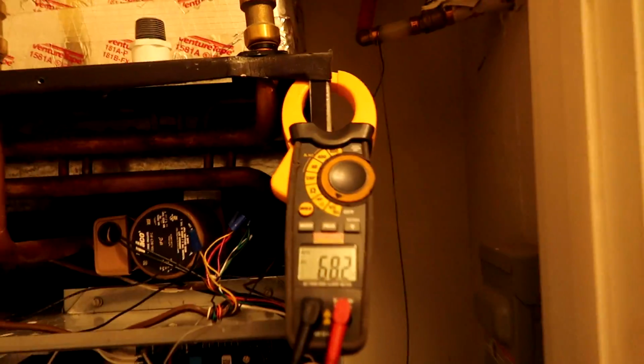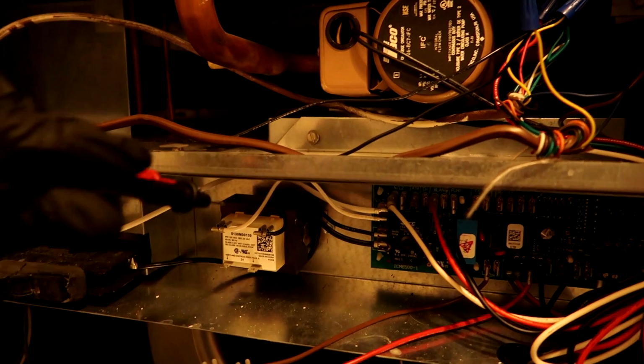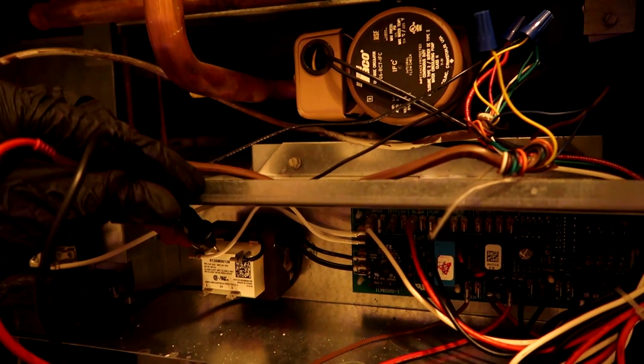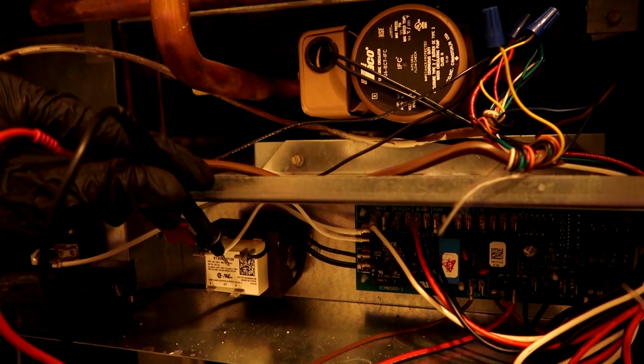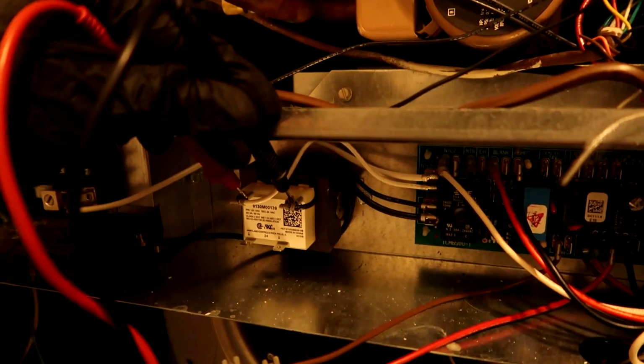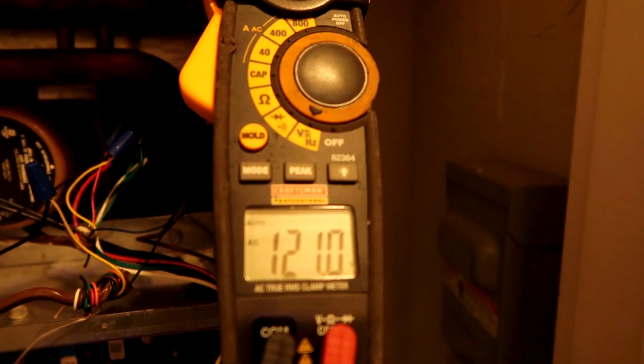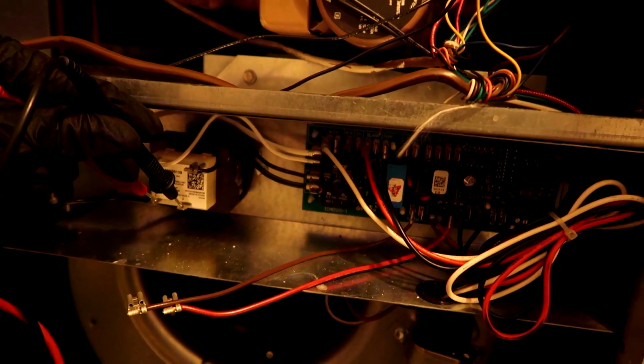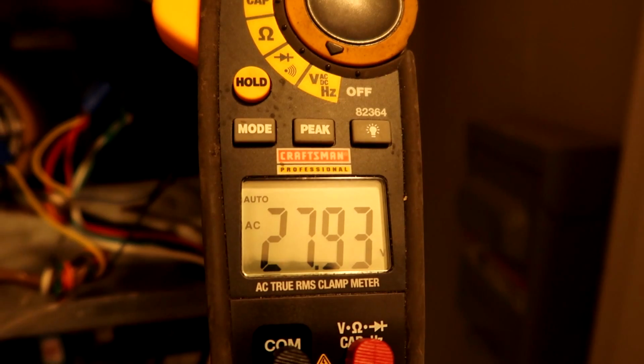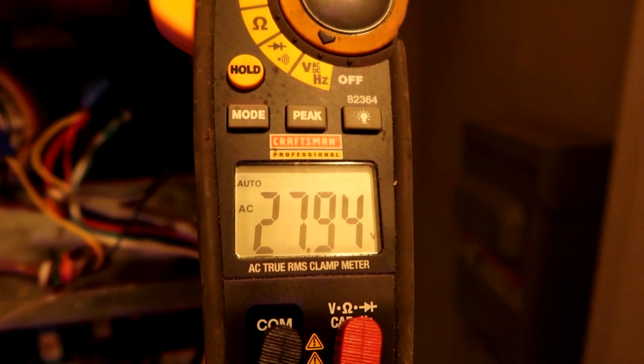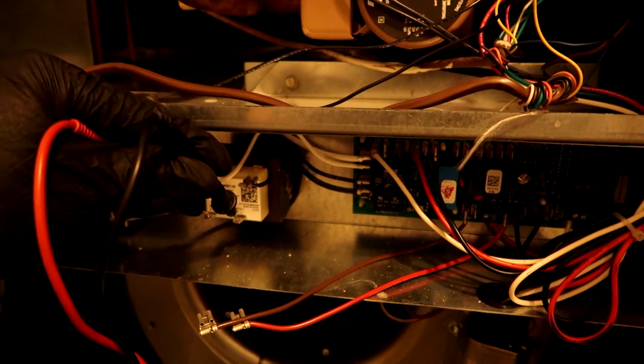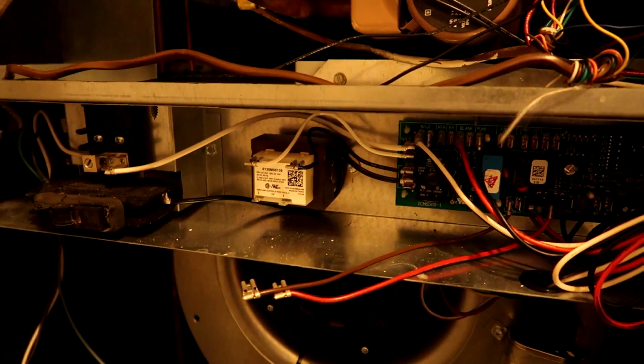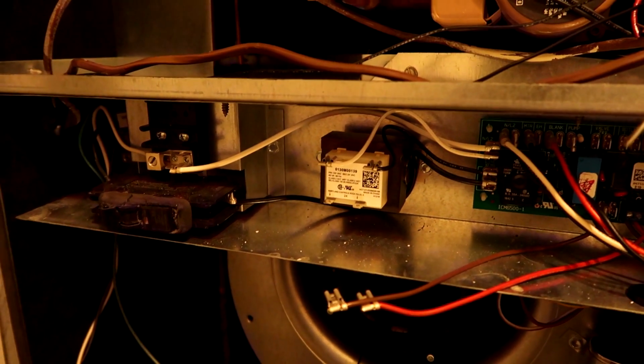Alright, Skid, we don't have any new transformers in the shop. Let's just see if we're getting high voltage here. Should have 120. Yep, 120, and we should have 24 volts coming out of the bottom, or around 24, 27. So the 27.9. So the transformer's still good. It was just heating up. That's what I smelled. I'm gonna roll the dice and hook it back up.